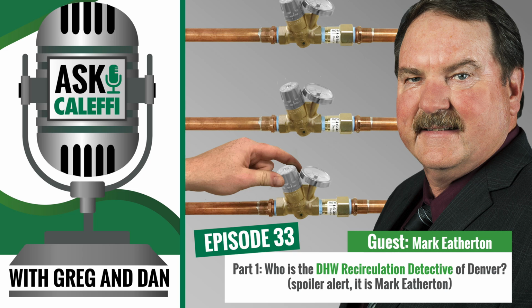And in reality, they could be helping maintenance by saying, what unit are you in? When does this problem occur? Is it always constant, or does it only occur between 6 and 8 a.m. or between 4 and 5 p.m.? And you at least get the ability to establish a pattern of complaints. And where is this complaint coming from? Is there a whole stack of apartments that are making the same complaint, or is it random throughout, or is it only the top floor?